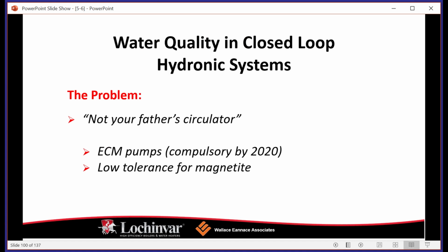Now, water quality can be a big issue. If you're doing new construction where you have all new piping, it makes your life easy because you can flush it out, fill it full of water, close it off, and it's good to go. But oftentimes what you're going to run into is swap outs on the fly where people didn't maintain their equipment, and now you're there in the middle of December getting screamed at because you need to change things right away. It's very important in those situations to take a look at the water that's in your system.